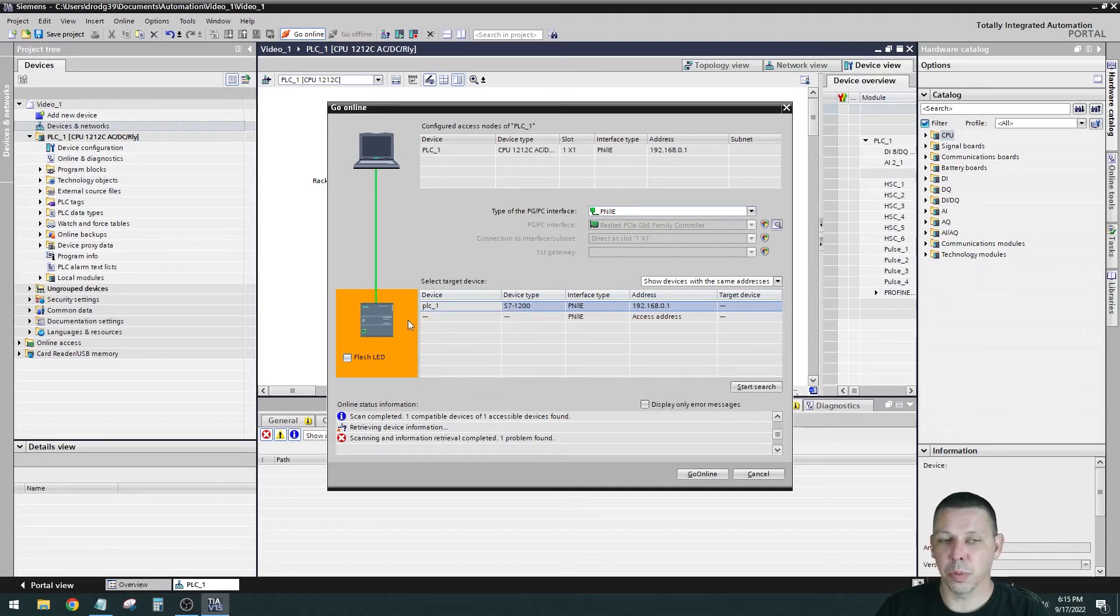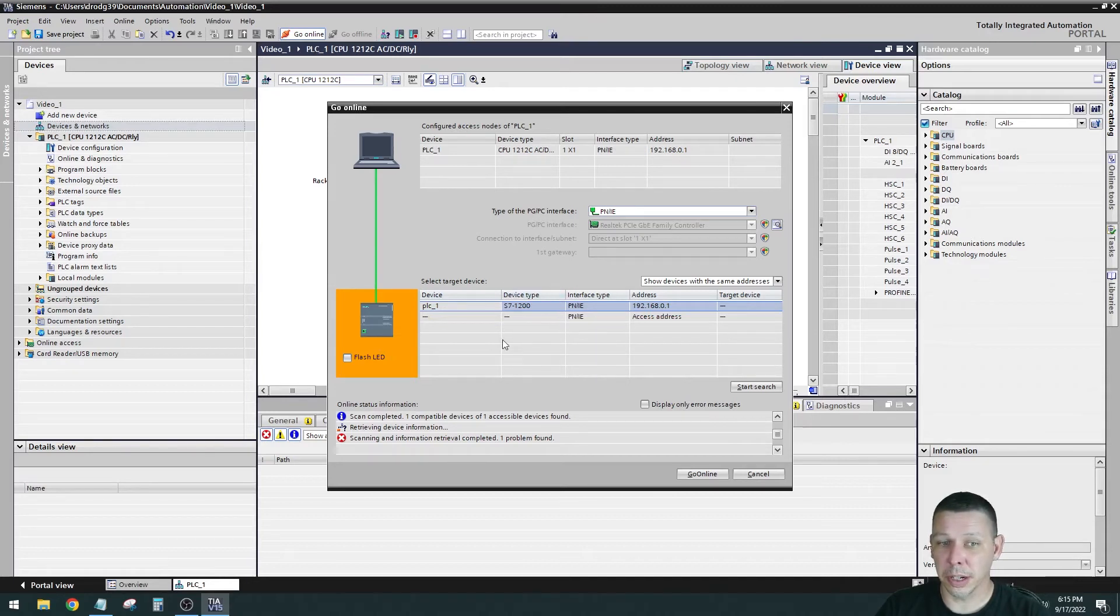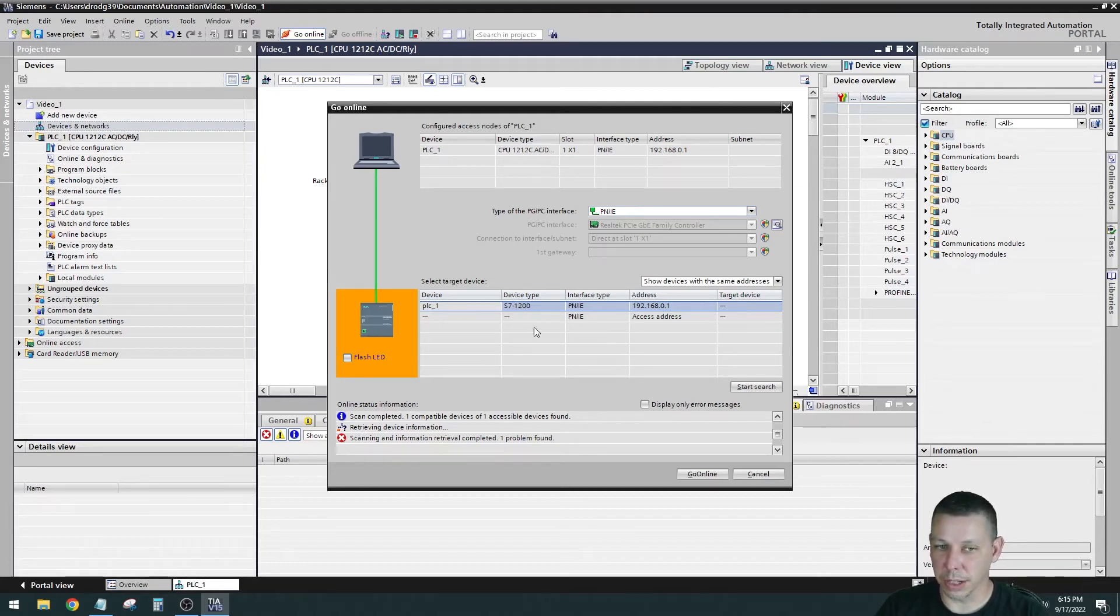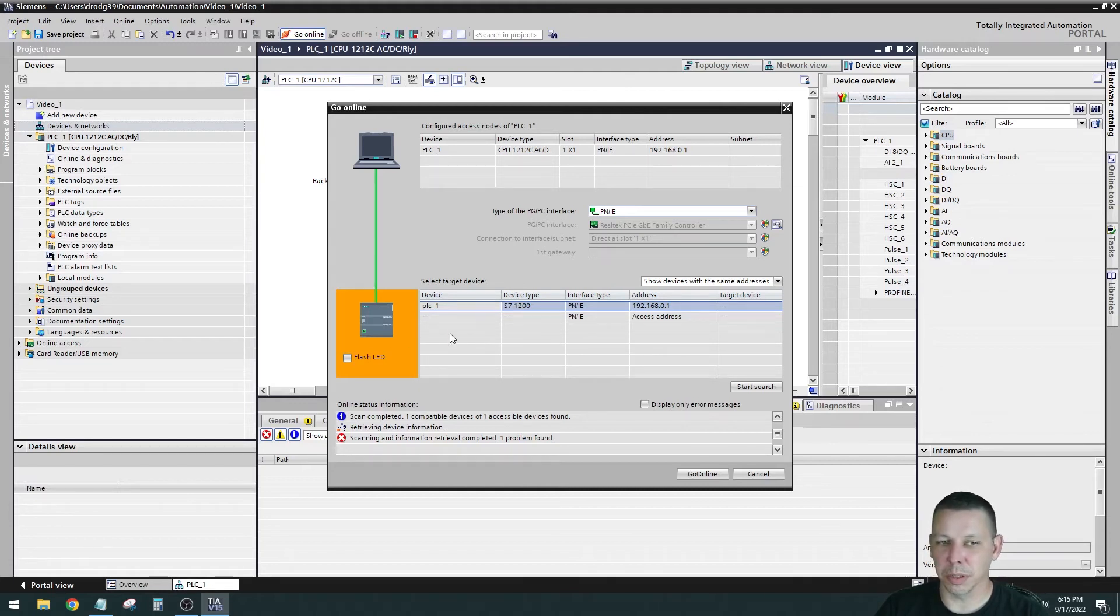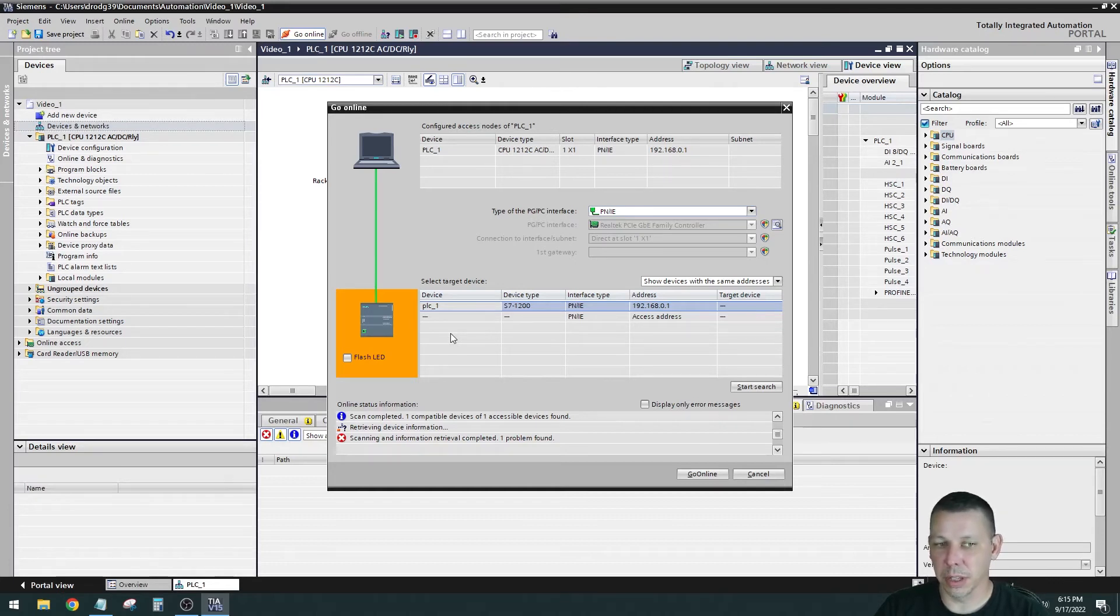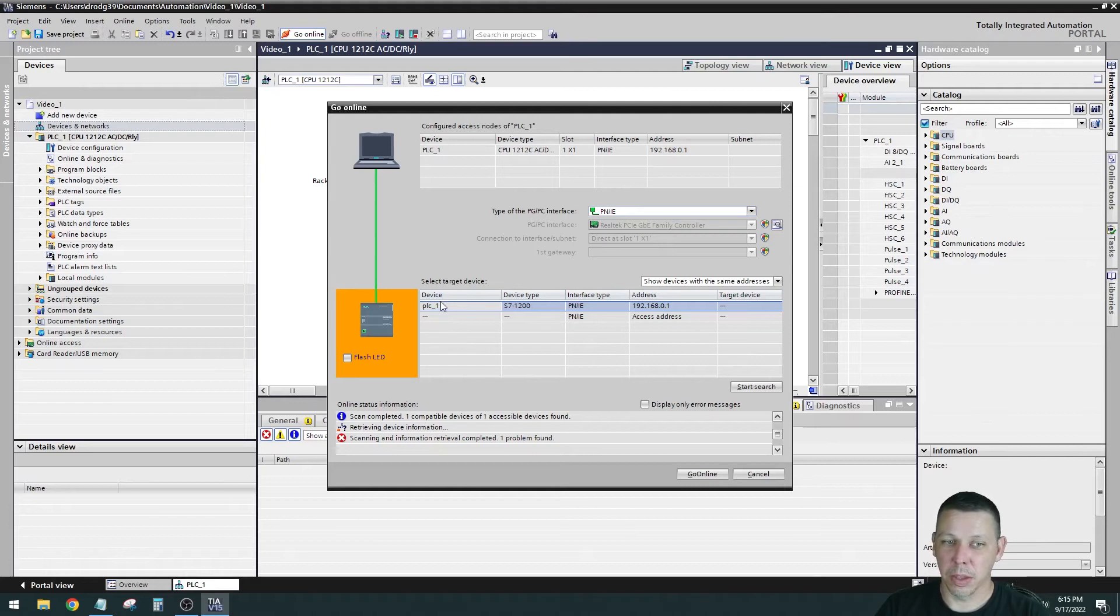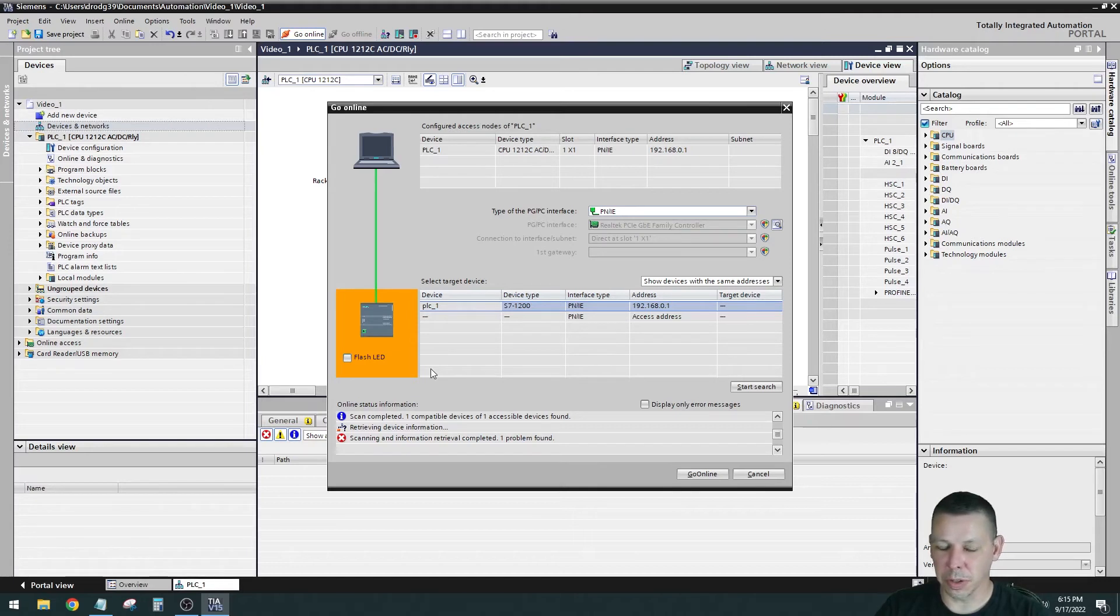So it's solid. Right here it says PLC1 S7-1200 and it has the address of the processor. If you're not sure which processor, if there's multiple processors listed here, you can select one and hit the flash LED and it'll flash the physical lights on the front of the processor to let you know which one you selected in this list. So you can go verify that you're connecting to the right processor.